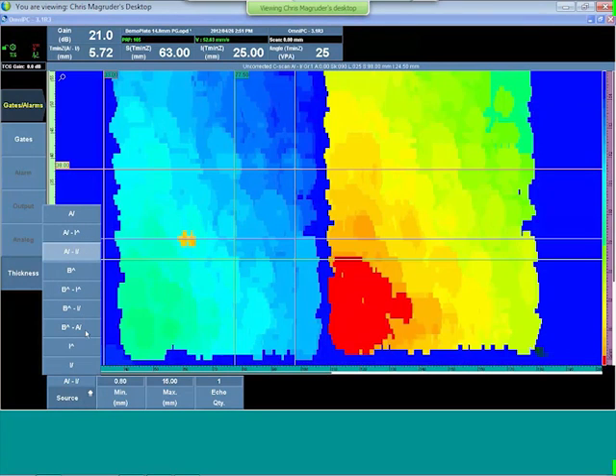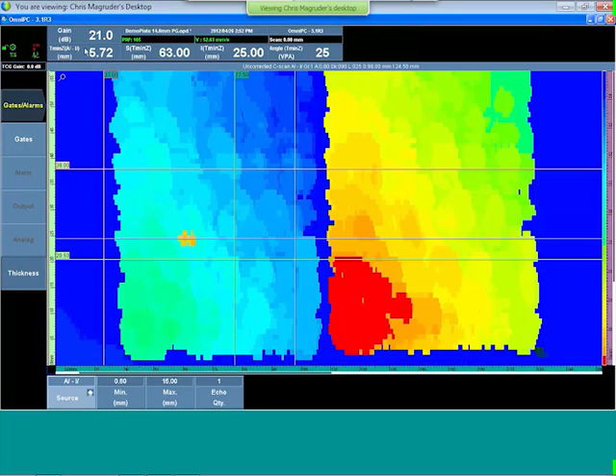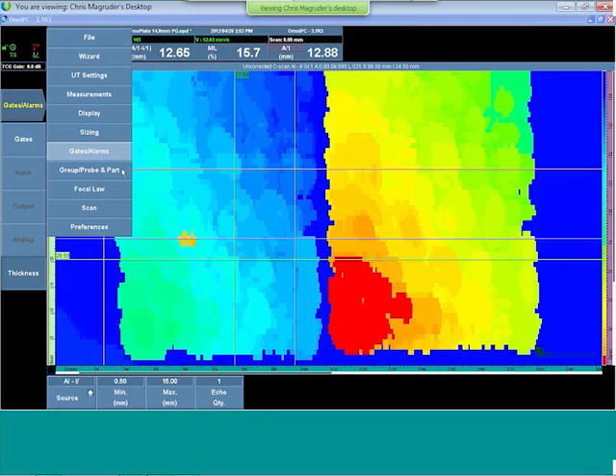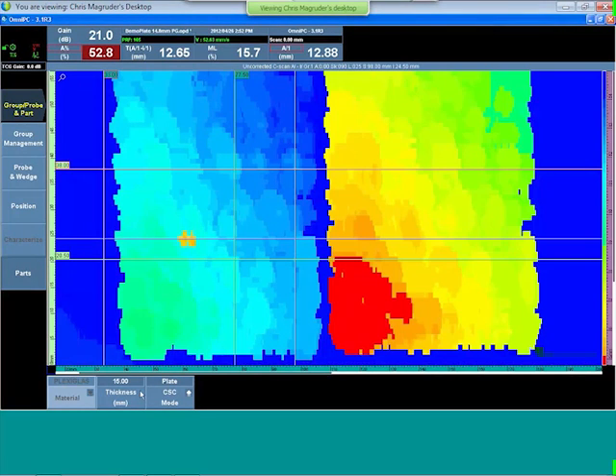Why would we ever use a B minus A gate configuration for the reading? For instance, if the pipe or vessel had a paint coating and we needed to eliminate that paint coating by using back wall to back wall, which is similar to what the conventional instruments call echo to echo, we can do that. So the lowest reading in the zone was 5.72 millimeters, and it occurred at 63 millimeters on this axis and 25 on this axis. It amounted to a metal loss of 15.7% based on the part thickness of 15 millimeters.